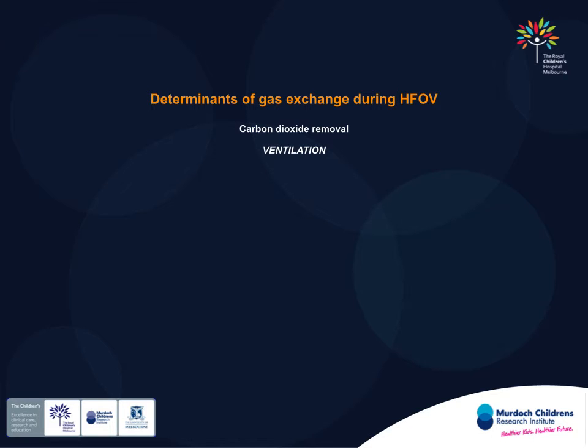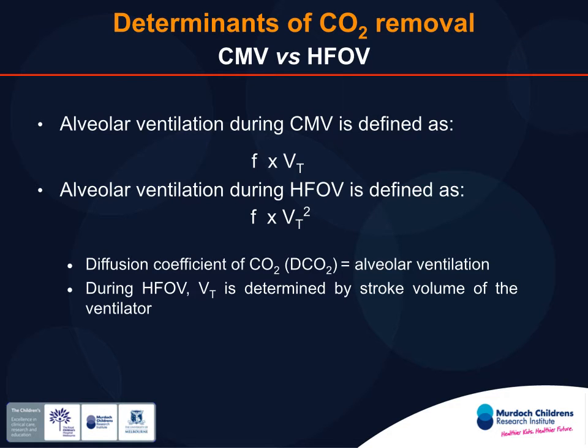So let's talk about ventilation. As I said earlier, alveolar ventilation is rate times tidal volume. On the oscillator, it's rate times tidal volume squared, okay? Or at least mathematically it is in the alveolus. And the diffusion coefficient of CO2, this magic number which is always shown around our DCO2, is just a fancy way of describing alveolar ventilation during high frequency, okay? The way tidal volume is achieved on an oscillator is from the stroke volume the ventilator applies to the system.